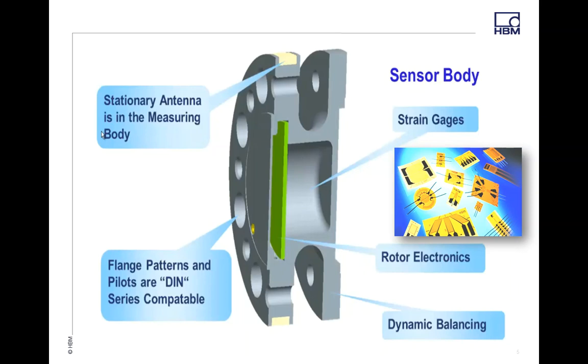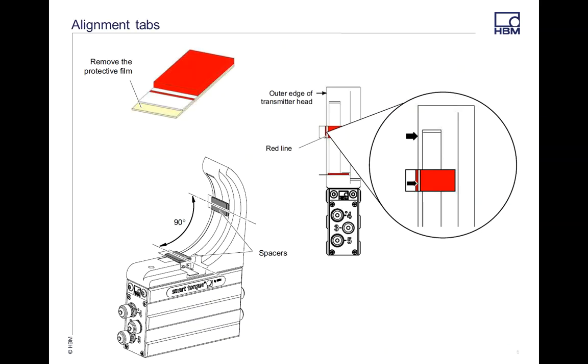So let's talk about alignment. When you first get your transducer, a lot of times there's a little stack of little red rubber spacers that a lot of people think are packaging. Well, that's not really the case. Those are actually alignment tabs to set up your rotor and your stator when you first get your transducer.